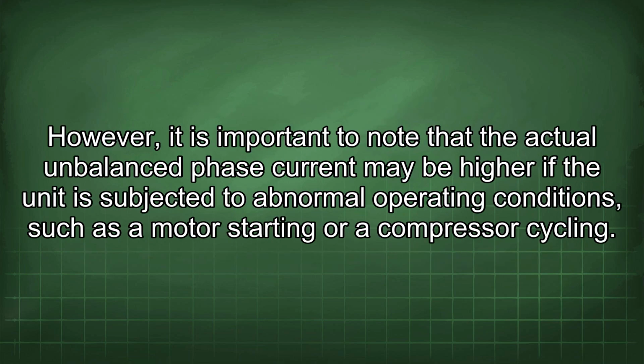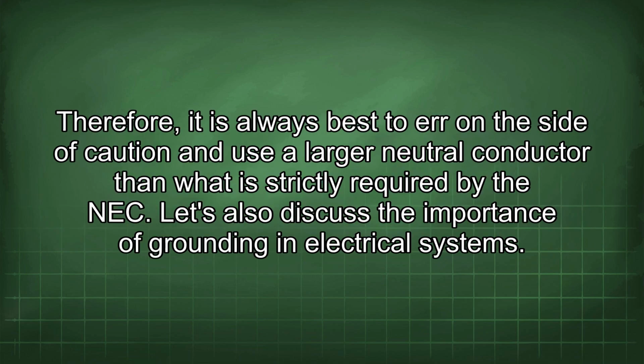However, it is important to note that the actual unbalanced phase current may be higher if the unit is subjected to abnormal operating conditions such as a motor starting or compressor cycling. Therefore, it is always best to err on the side of caution and use a larger neutral conductor than what is strictly required by the NEC. Let's also discuss the importance of grounding in electrical systems.